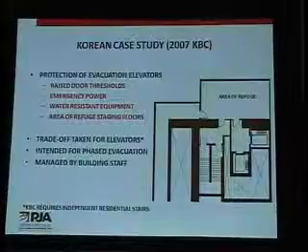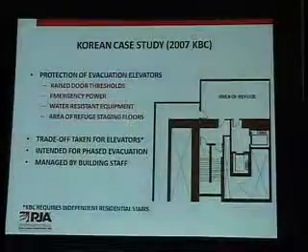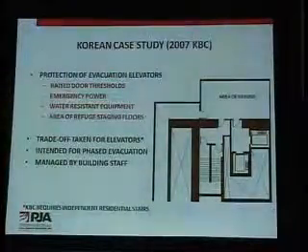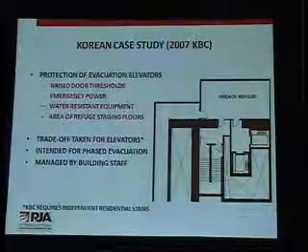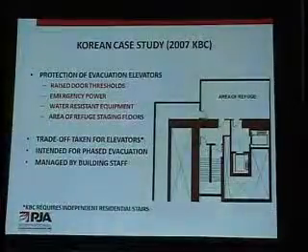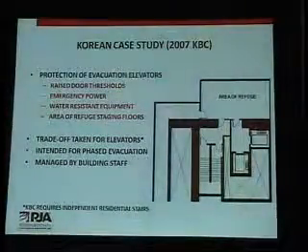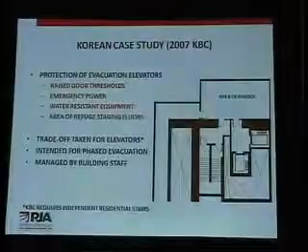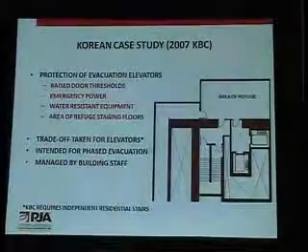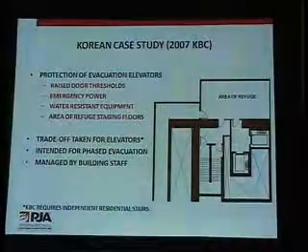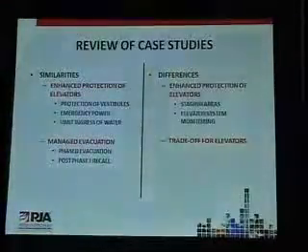And in this case, technically trade-offs weren't taken for elevators in terms of an overall fire strategy, but in terms of the Korean building code, trade-offs were taken because the Korean building code does not allow residential stairs to share stairs with any other occupancy. In this building, the residential occupancy was at the top of the building with restaurants above them and office below them. We would have required 8 stairs in the building because there are 2 separate towers, which really wasn't sustainable. So I guess at the end of the day, we did take a trade-off.